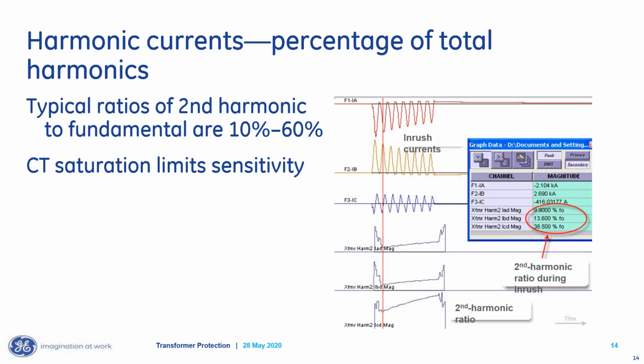The other thing that I really haven't talked about that I should talk about is transformer inrush. When we first energize a transformer, typically we will close one of the breakers. Typically, that is the higher voltage breaker. By closing the higher voltage breaker first and energizing the transformer that way, there's less transformer inrush. And transformer inrush is basically a large current that flows into the phases and flows out of the phases.